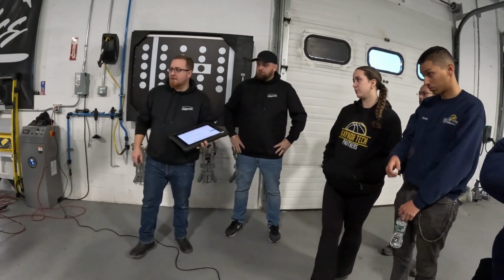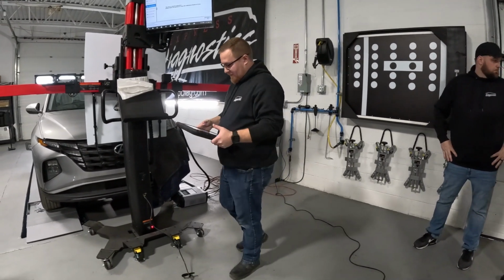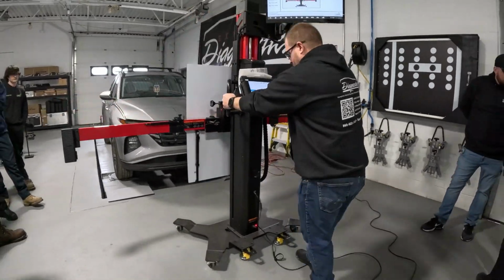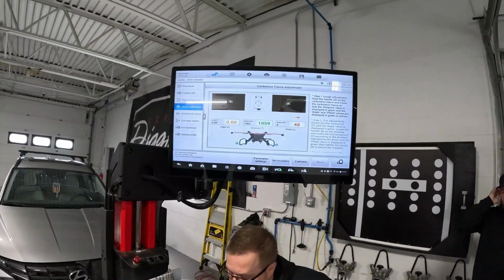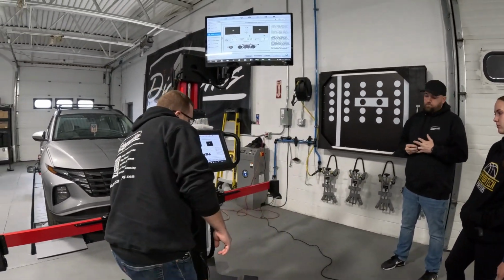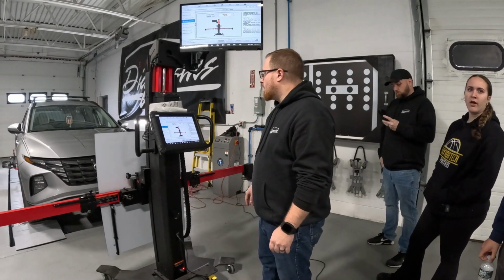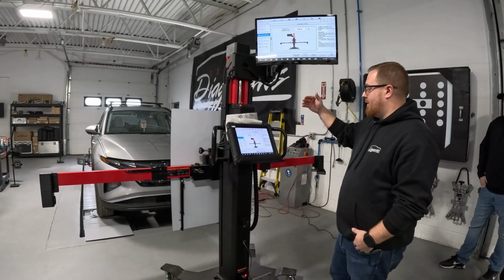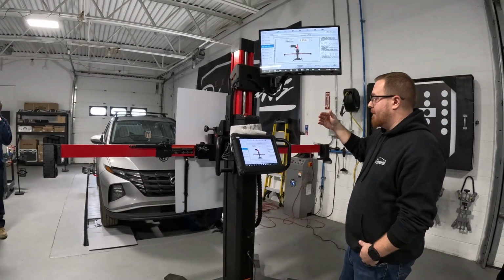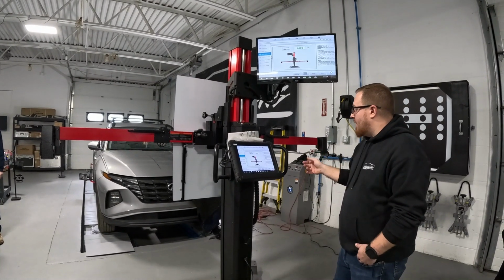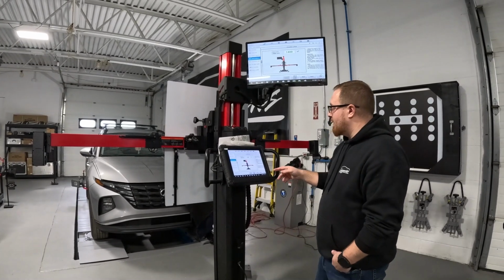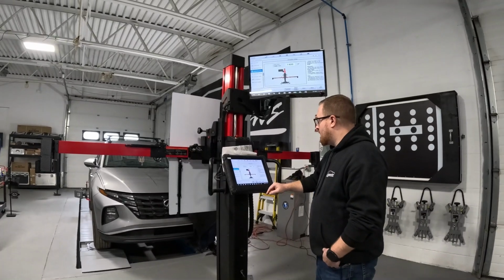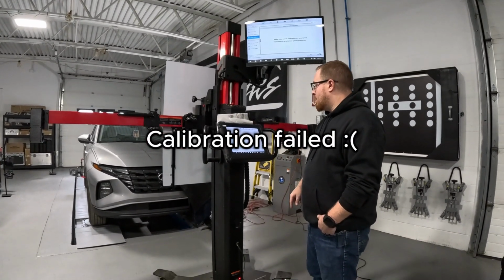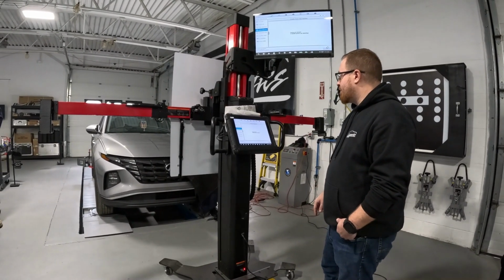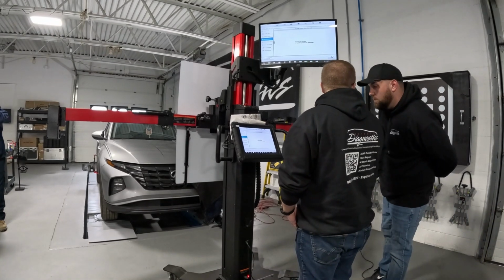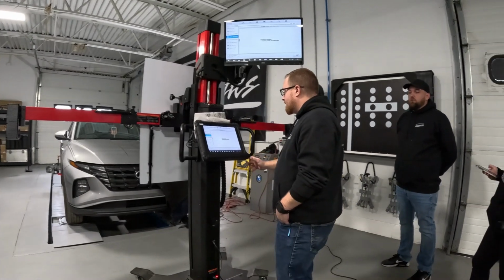All right, next step is the second part of the calibration. We have 5 minutes to get it into the second position. Because we moved the calibration frame farther back from where it was before for the first calibration, we did have to make all our adjustments again that we did before, but as you saw, it didn't take very long. When we're at shops, it takes a little bit longer. See? Perfect. So this is again another reason why we like showing everybody this.